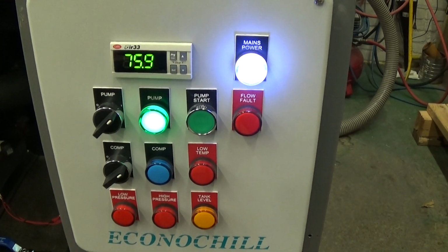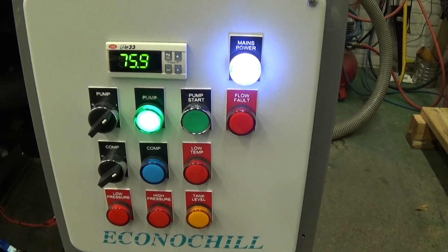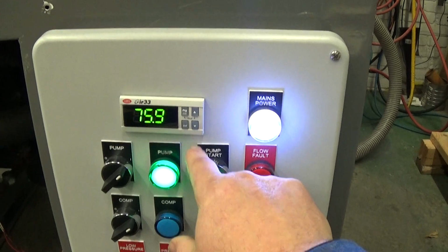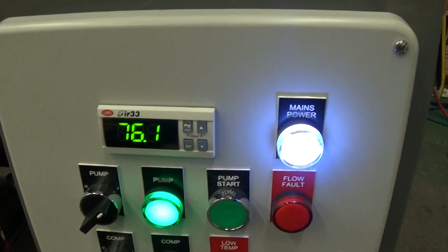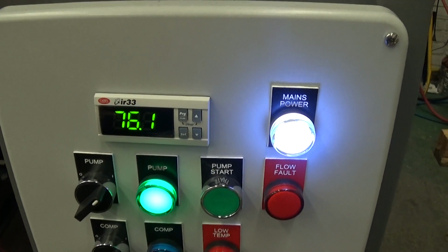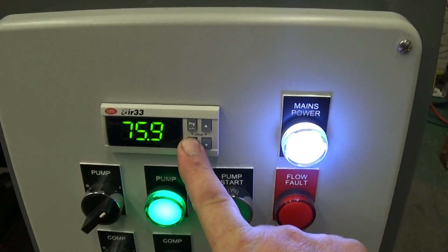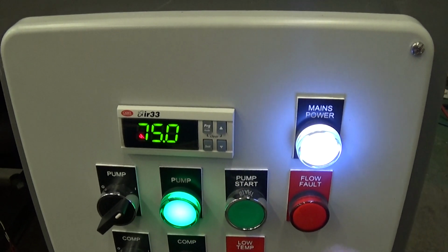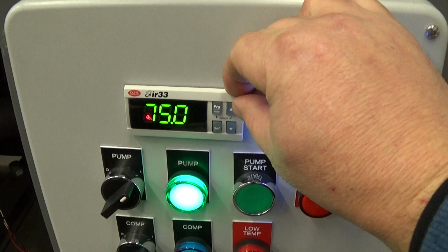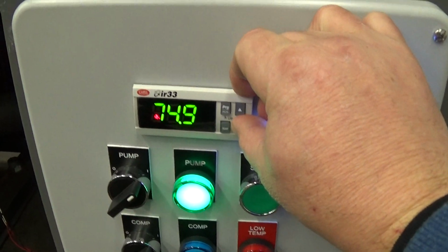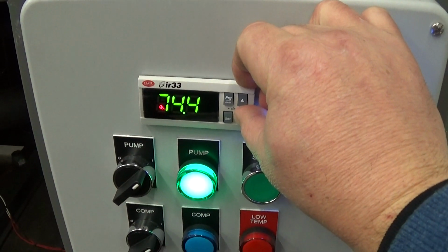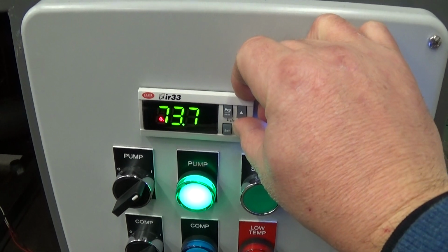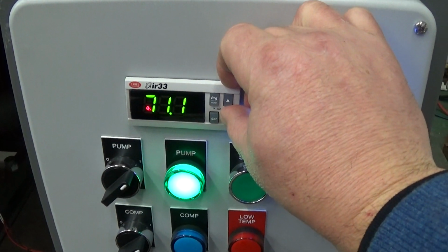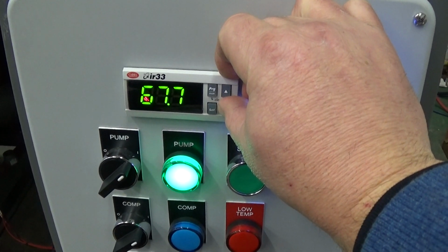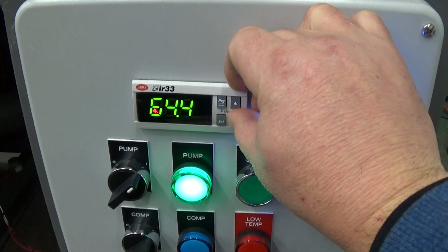In this case here, we're going to run a test and cool it down to 45 Fahrenheit. And all you need to know is how to change the set point. Just press set. It's going to say ST1. What it's set at, it starts blinking. Then use the up or down arrows to adjust it. In this case here, we're going to scroll down to the minimum 45. After you actually hit 45 on this unit, it'll go back up to 75.